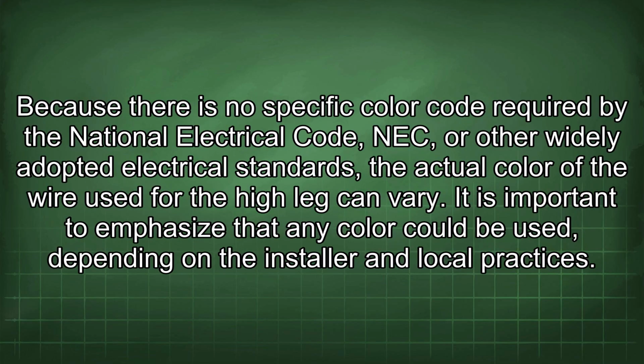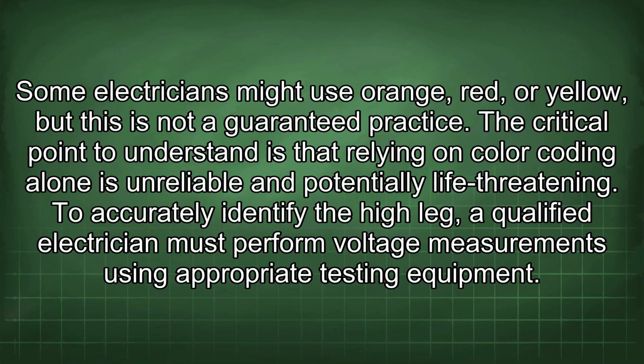Because there is no specific color code required by the National Electrical Code, NEC, or other widely adopted electrical standards, the actual color of the wire used for the high leg can vary. It is important to emphasize that any color could be used depending on the installer and local practices. Some electricians might use orange, red, or yellow, but this is not a guaranteed practice. The critical point to understand is that relying on color coding alone is unreliable and potentially life-threatening.